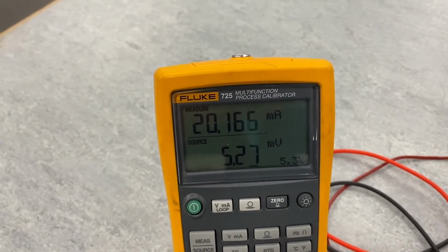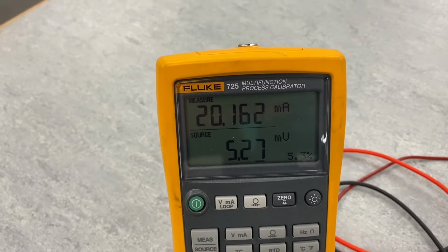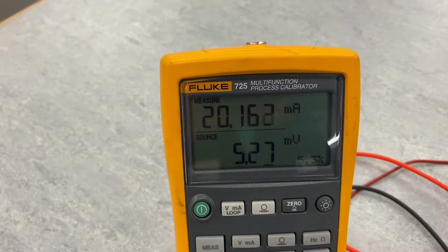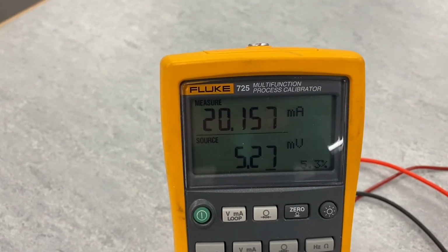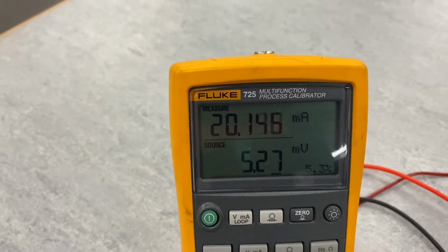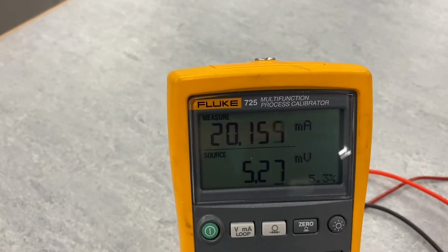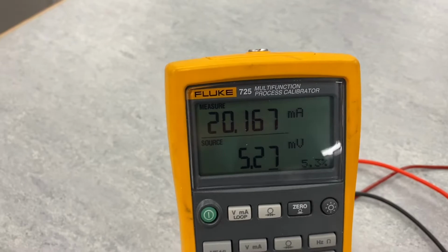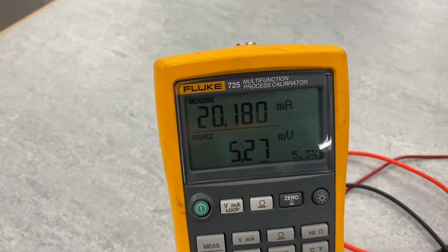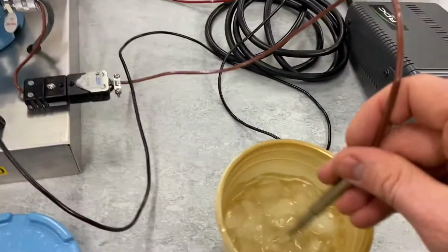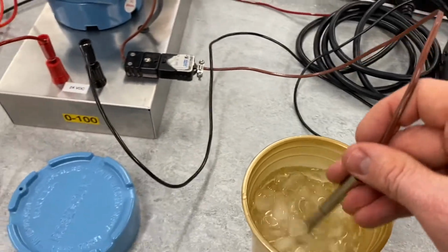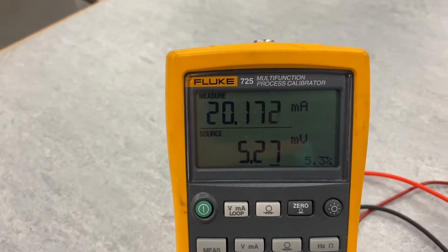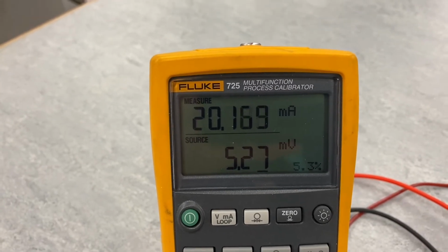I'm just going to agitate the ice bath here. And you can see also we would want to do a little bit of a span adjustment there to make our meter up here read the 20 milliamps that it's supposed to. So make sure we're agitating this ice bath over here when we're making our adjustments, and calibrate our transmitter to 0 to 100 degrees C with a 4 to 20 milliamp output.